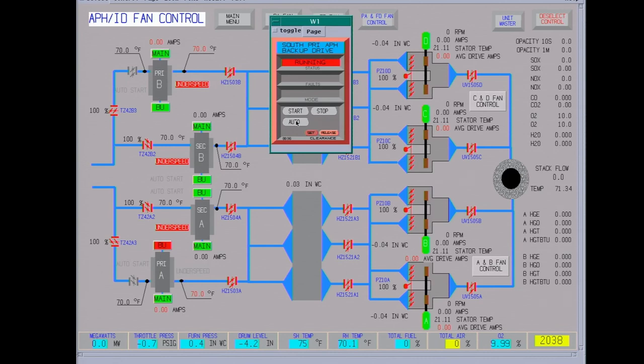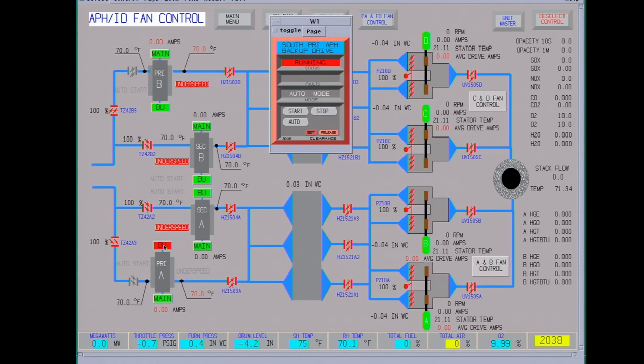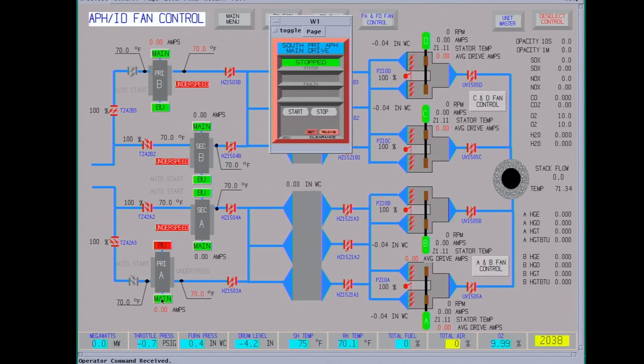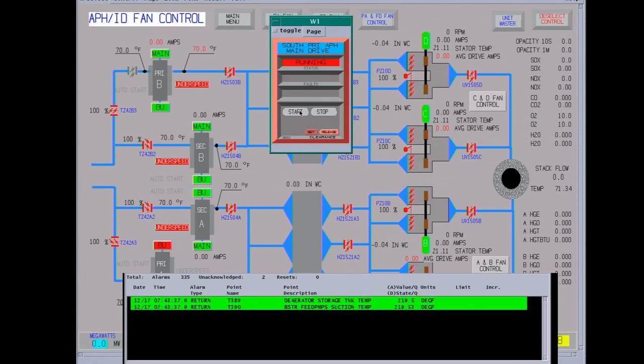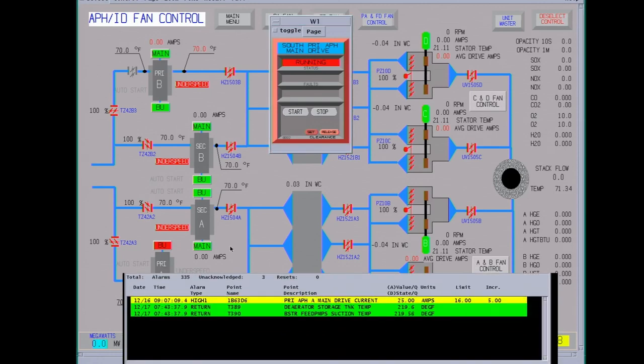Usually you'd start the backup, now I'll put it on auto so that it will be in auto once we start the main. Usually you'd wait until you get a call back from the person in the field that there's no rubbing, you know where it started. Okay, this is one of the permissives to start the ID fans. You want to watch your current when you're starting up.